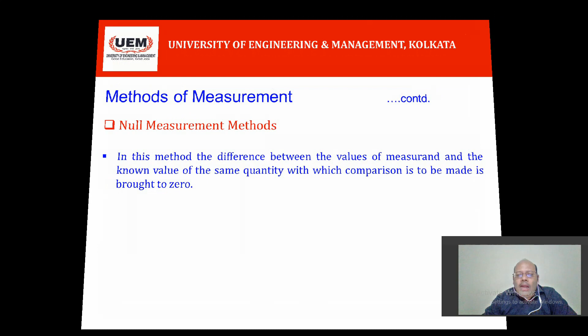But another very important example of a null type instrument is the dead weight pressure gauge. Dead weight pressure gauge means a piston is placed in a cylinder, and on the upper face of the plunger, which is attached to the piston, known weights are placed, and datum leveling is done. The weights are adjusted one by one such that the pressure from the fluid is balanced by this dead weight, and at the balanced condition the datum line is obtained by the lower face of the piston by adjusting the weights on the upper face of the plunger. In this way, a null type instrument is adjusted.